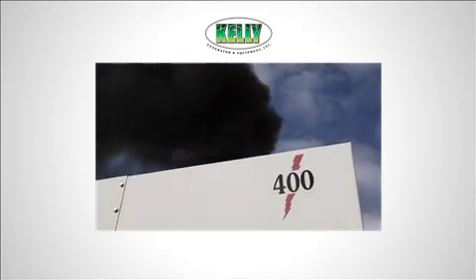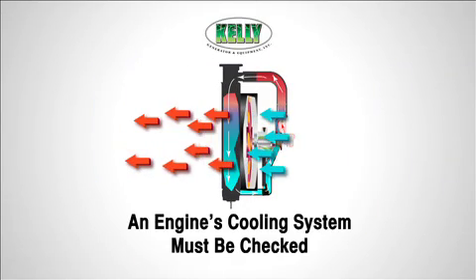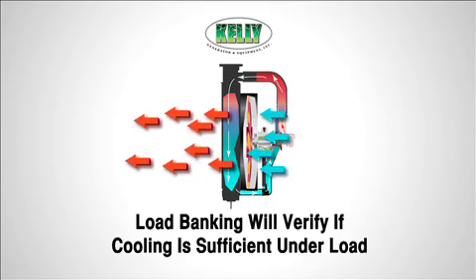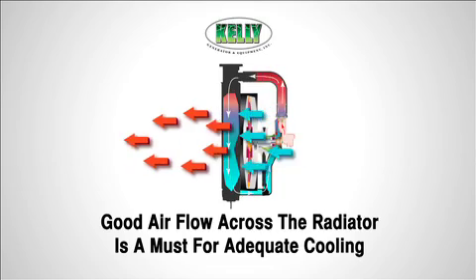A frequent sign of an engine suffering from wet stacking is excessive black smoke on startup. Another cause of underperformance is problems with an engine's cooling system. Load banking will verify if cooling is adequate for the generator to carry the load without overheating. Air flow over the radiator is critical for cooling.